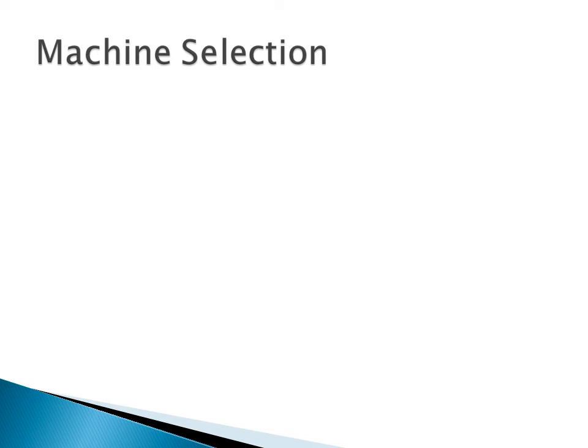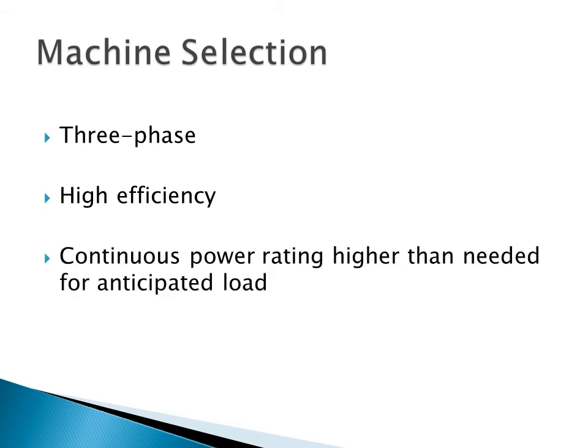Okay, so for machine selection, we're going to want to choose a three-phase machine. They have ratings much higher than single-phase, and they're much more common. You're going to want high efficiency. This will reduce the copper losses inside. It should have a continuous power rating higher than the needed rating for your anticipated load. This is because when they're operating in generating mode, the stresses are a bit higher, and the core may be a little bit more susceptible to saturation. And then, whatever type of enclosure you need will depend on the installation, but it may need to be waterproof, dustproof, totally enclosed, fan ventilated, etc.